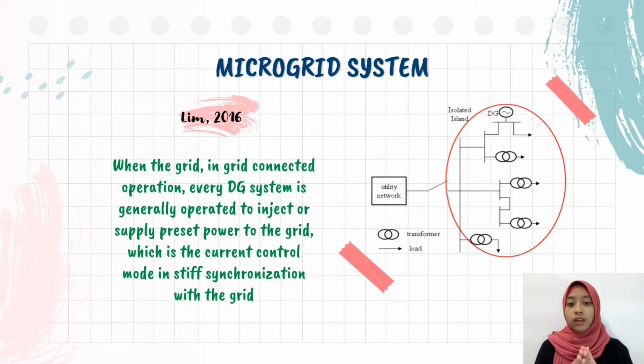Right, let's move on to microgrid system. Lim stated that when the grid is in grid connected operation, every DG system is generally operated to inject or supply power to the grid, which is the current control mode in stiff synchronization with the grid. These are the single line diagram of the studies.